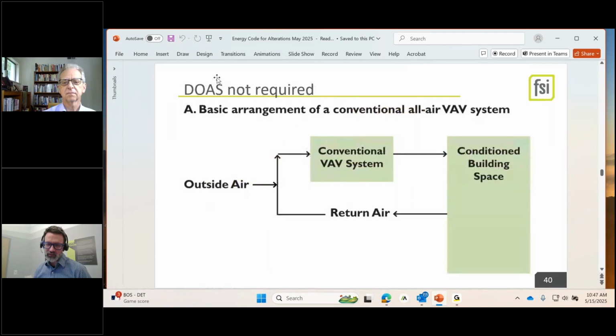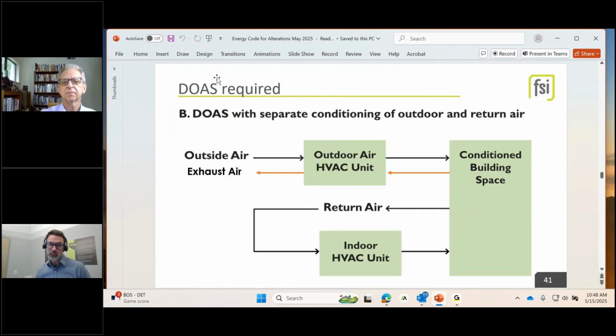Every mechanical engineer on the phone is going to roll their eyes, but it's important to say this. Conventional systems took return air, mixed in outside air, reconditioned the whole thing, sometimes overcooled and then reheated at the zone level. We weren't thinking hard about energy efficiency. So what is now required by DOAS, hit the next slide, separates the indoor heating and cooling loads from the outside air heating and cooling loads and requires that we do energy exchange between the exhaust, like bathroom exhaust, and the incoming air, such that we get back on the order of 65 to 70% of the energy that we were throwing overboard in old buildings. We were just exhausting those bathrooms out instead of trying to get some of that energy back. So it is actually a lot more efficient.